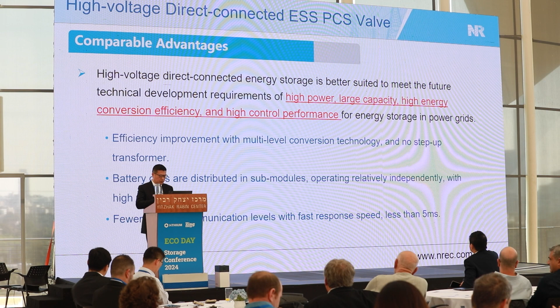Also for this kind of solution, the beginning investment is a little higher than that centralized with the transformer, but the efficiency can be increased maybe 2 to 3%, and also the total response speed - when you do the control, response speed can be less than 5 milliseconds.